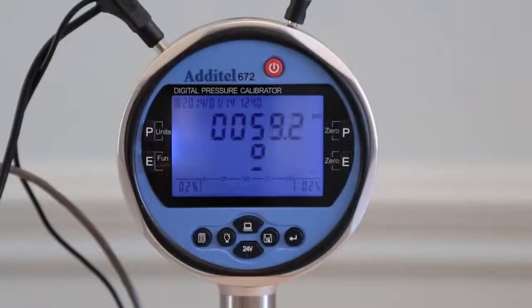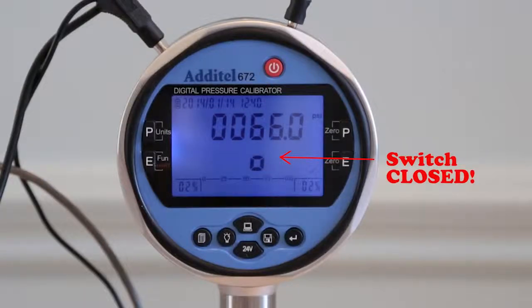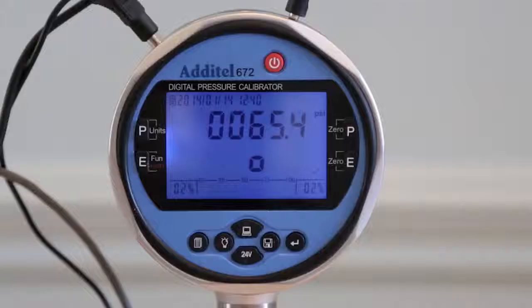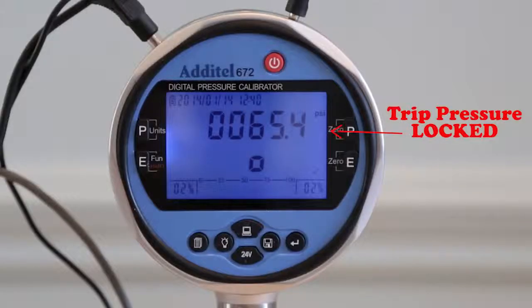For pressure switch testing, the 672 stores set and reset points in internal memory, which can be downloaded via RS-232 port to the free Additel/Land software to generate reports and certificates. The display can also be set up to hold the trip value on the display for manual recording.